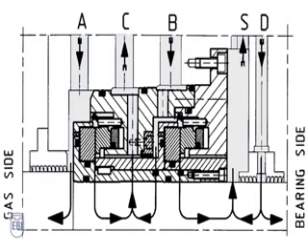The tandem arrangement of two gas lubricated mechanical seals with intermediate labyrinth plus atmospheric labyrinth or segmented carbon rings reliably prevents any leakage of product gas towards the atmosphere. The secondary gas seal serves as a backup seal in case of a breakdown of the primary mechanical seal.